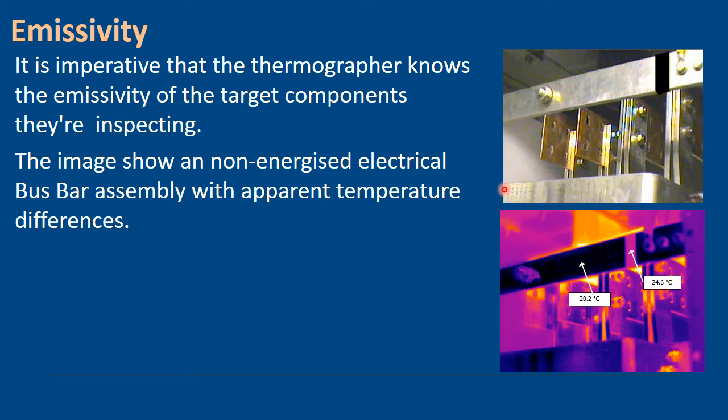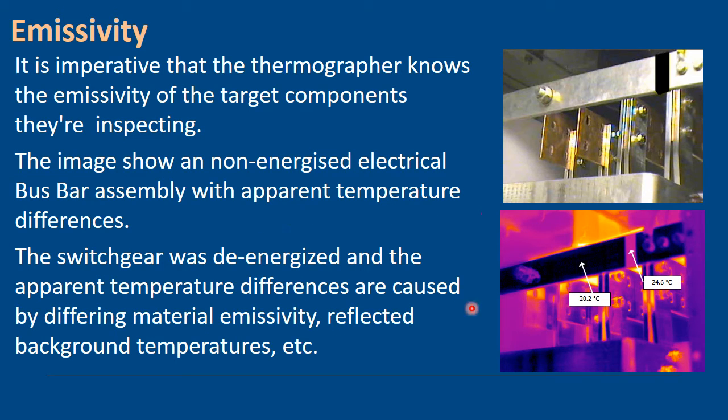We're seeing here there's a difference of four and a half degrees on something that's never been switched on, the same length of bus. Very important to understand that relationship, and that all of these temperature differences really are caused by emissivity of different materials, different reflections, the background temperatures, etc.